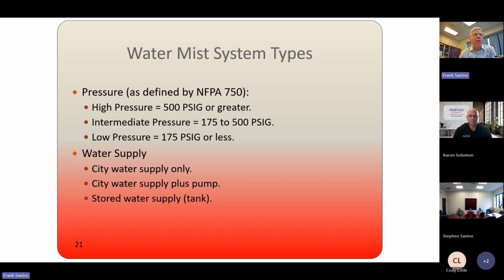Or just compressed air. So the different types of water mist, as defined in NFPA 750: high pressure is above 500 PSI, intermediate pressure water mist is 175 to 500, and low pressure is anything under 175. For the water supply requirements, you can tap off your city water supply. You can do a city water supply plus a pump, as I described in that medical facility. And then you also have the option, if you don't have any water at all, to do a stored water tank. And that's where water mist really comes into play.